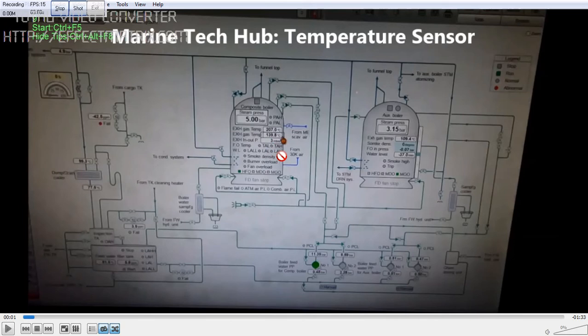So one important thing which you should understand is that when you are changing the sensor, you should put the range correctly. So in the computer you have to put the range 0 to 500. That is the range of the temperature sensor. But in case you put it 0 to 450, that time you will get a wrong reading here.